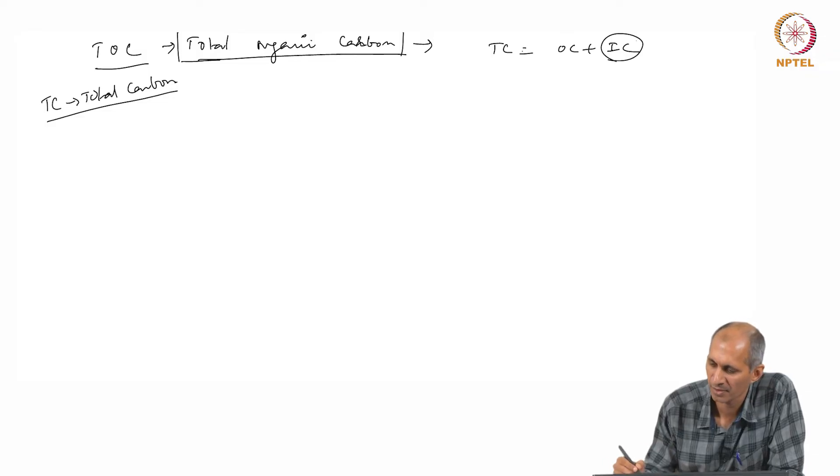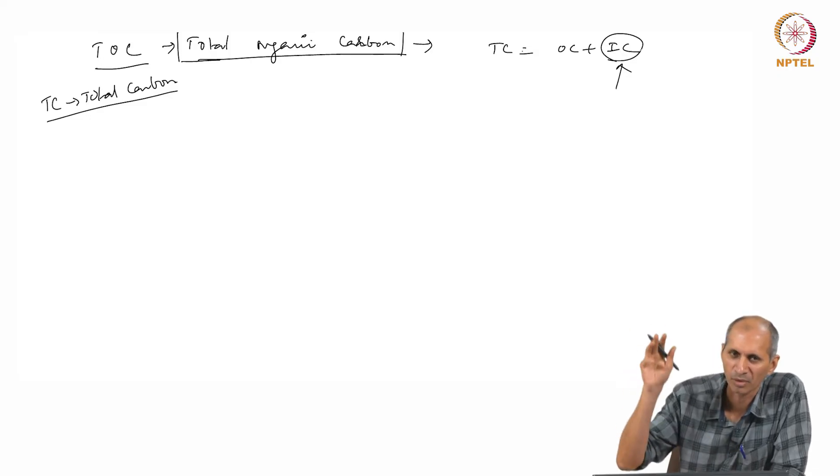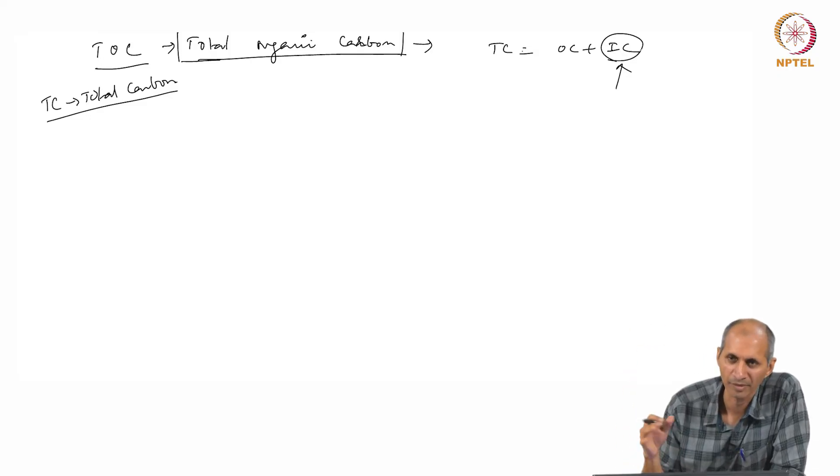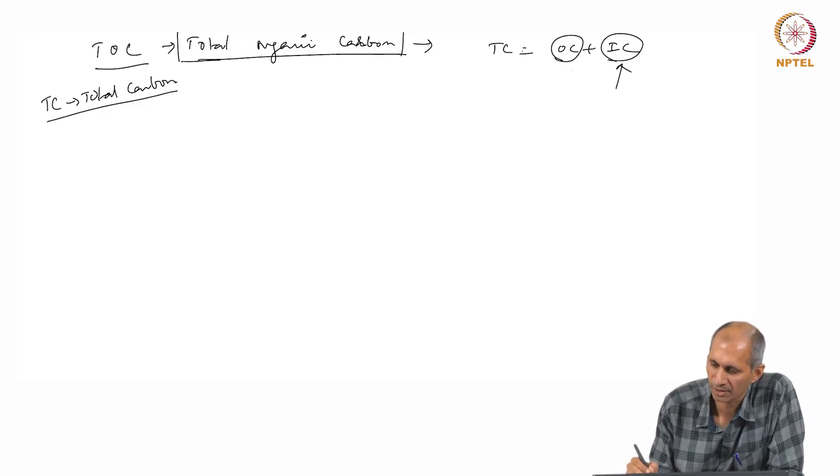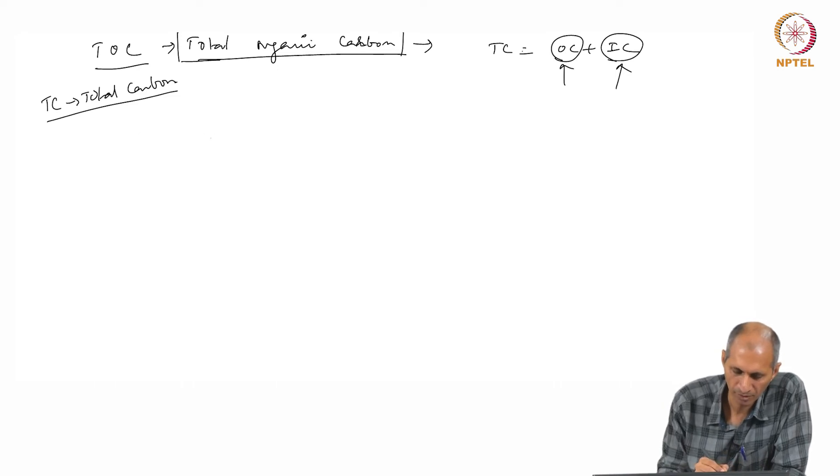The instrument itself does not care about OC or IC; you have to remove IC before you do the OC. The way we remove IC is we add something that will release all the carbon dioxide that is there associated with carbonate. Usually we do it with some acids like HCl. We add a little bit of HCl; it will all go to CO2, you have to bubble it out. Then the rest of the carbon that is there is all organic carbon.